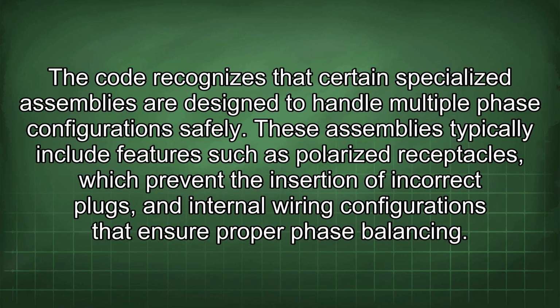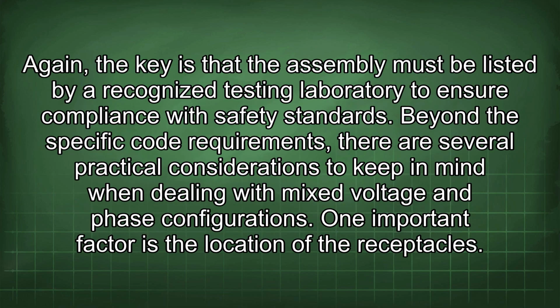The code recognizes that certain specialized assemblies are designed to handle multiple phase configurations safely. These assemblies typically include features such as polarized receptacles, which prevent the insertion of incorrect plugs, and internal wiring configurations that ensure proper phase balancing. Again, the key is that the assembly must be listed by a recognized testing laboratory to ensure compliance with safety standards.